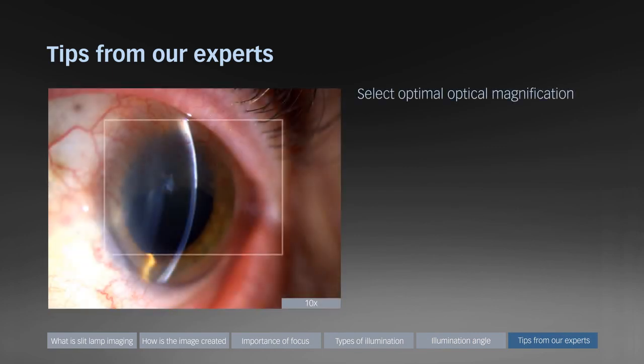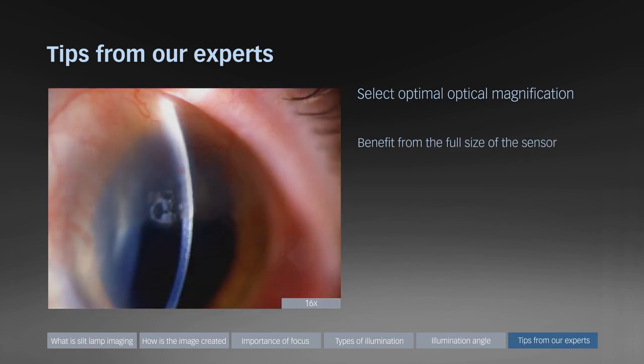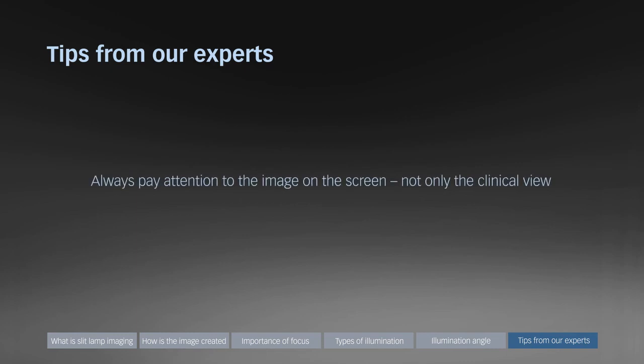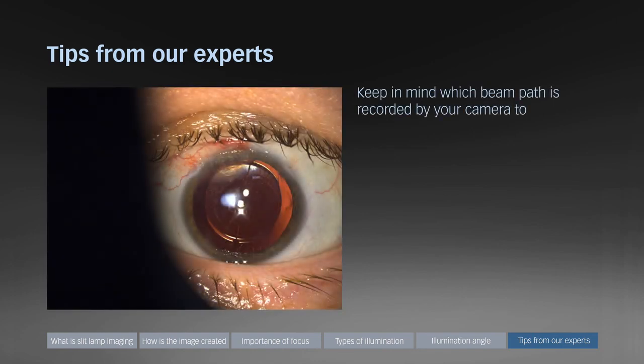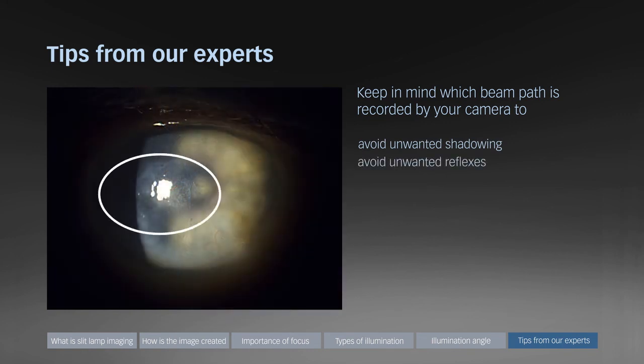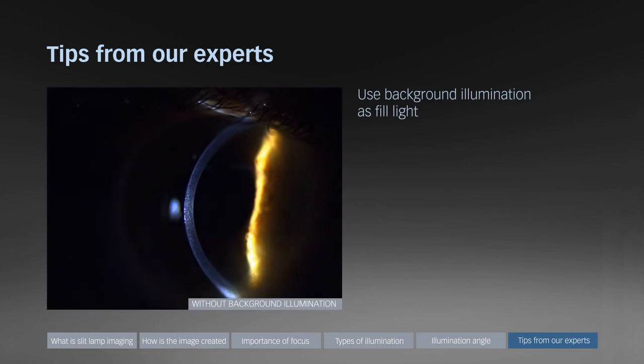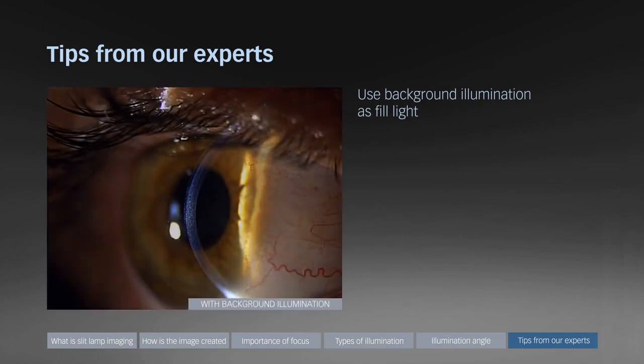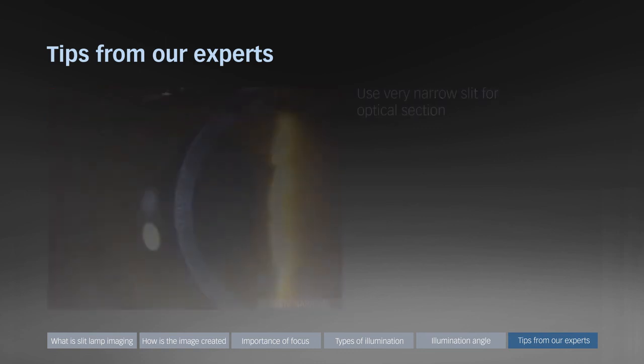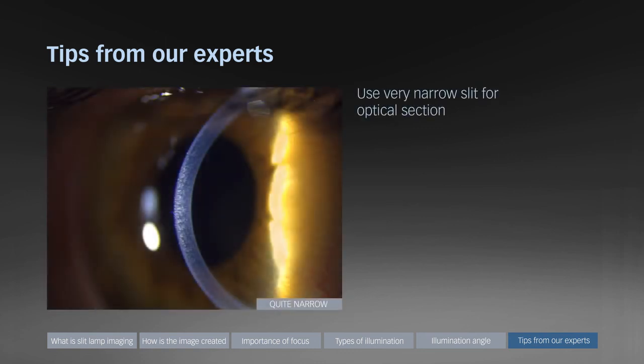This last section provides general imaging tips from our experts. First, select optimal optical magnification so you benefit from the full size of the camera sensor. Always pay attention to the image on the screen, not only the clinical view. Keep in mind which beam path is recorded by your camera to avoid unwanted shadowing and reflections. Add background illumination to improve orientation within the image. Use very narrow slit illumination with maximum slit intensity for optical sections, otherwise you will lose detail.